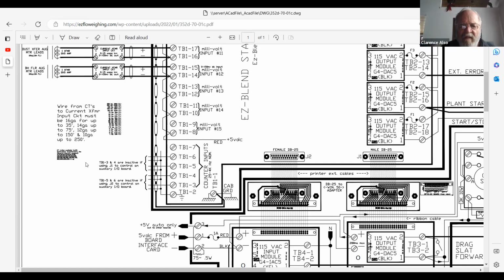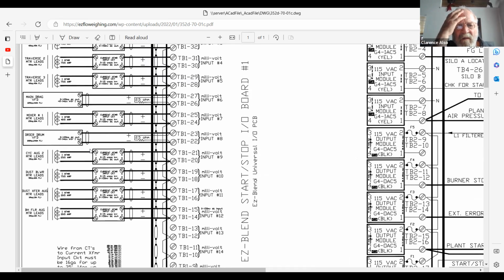You can see on the left there, they got some millivolt input there. I'm not sure if we're missing some, go up a little bit, straight up from there, David. Okay, yeah, basically that's current transformer input kind of thing. On the other side there was your IO, with the yellow stuff that was input. And then there's the output there, telling things to come on and off. And there's one that says plant start. You can see right there near the bottom right. It's a black one. This is, okay, we're gonna start the plant. So the button control says, okay, we're ready to start the plant.